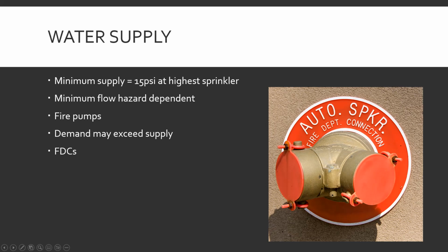Water supply to standpipes. Well, standpipes later, sprinkler systems. The minimum supply, regardless of how it comes, has to be at least 15 psi at the highest sprinkler. It's according to the NFPA book. The minimum flow for the system is dependent on the hazard. If it's a sprinkler system in a house, it'll probably be pretty low. If it's a sprinkler system in a wood shop or some big fuel load place, a big store, it'll probably be a lot higher. It's all dependent on what's in the building.